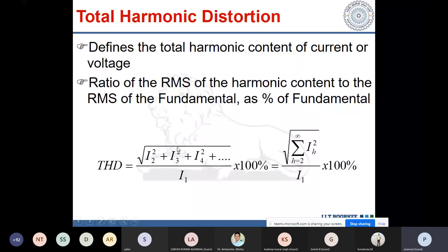But what happens if your load is very light? Like a motor that is lightly loaded. Lightly loaded means the fundamental current is very small, but harmonics may be of the same magnitude. In that case, it appears THD is very high, meaning very poor quality. And just to avoid this confusion, we use total demand distortion. So rather than dividing by the fundamental current, we divide by the rated current. Whether it is lightly loaded or heavily loaded, rated current remains the same. And then if total demand distortion is within the permissible limit, 5%, it's fine.